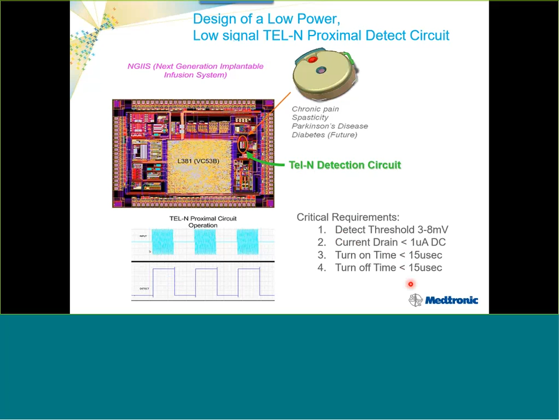Here's another example for another device. This is for the nervous system, we required medical telemetry, so we call it the TEL-N circuitry, medical telemetry. It uses amplitude shifting. One is a high amplitude, the 0 is a low amplitude. And we have 4 key requirements. Detect threshold had to be in a range of 3 to 8 millivolts. The current drain, because we want to have long battery life, had to be less than 1 microamp. The turn on time and turn off time, the responsiveness, had to be less than 15 microseconds.